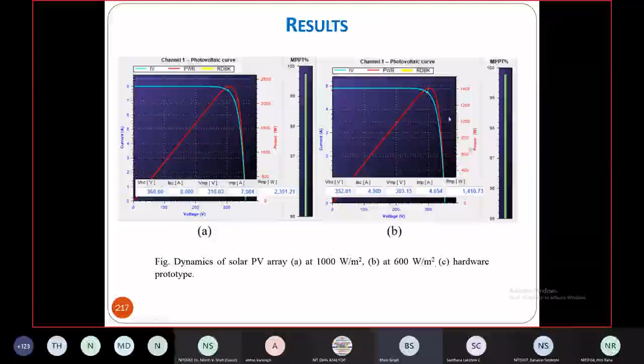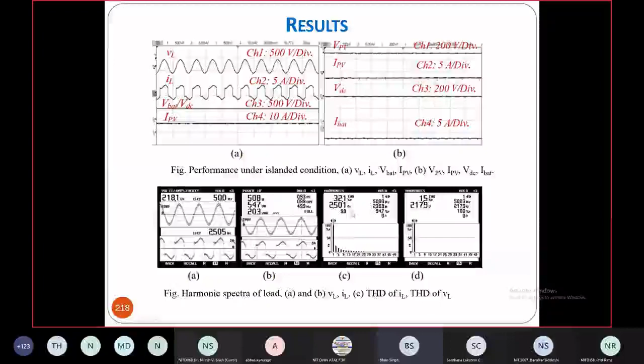Even in isolated or islanding mode, you can see the voltage remains sinusoidal despite feeding a non-linear load. The THD of the voltage is 1.5%, while feeding a load of 32.1% THD, in UPS mode during islanding.